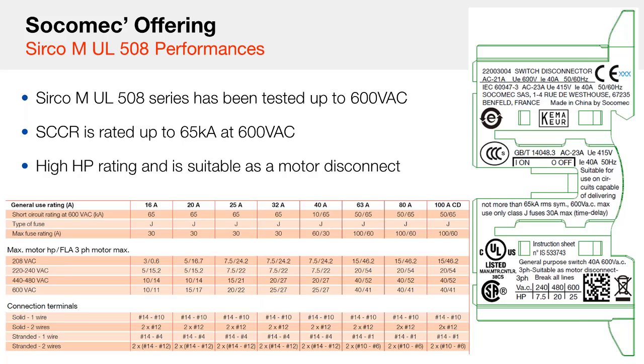So looking a little deeper into the characteristics of the Socomec UL508, at Socomec we choose to test for a higher fault short circuit rating. The Socomec UL508 switches have up to 65 kA short circuit rating. It can also be used up to 600 VAC, and it has high HP ratings, making it a really suitable motor disconnect. The short circuit rating is something that we test, so when it's used with a class J fuse, you can achieve that high short circuit rating of 65 kA. Otherwise, the standard one, I believe, is 5 kA. So it's just something that we do at Socomec.